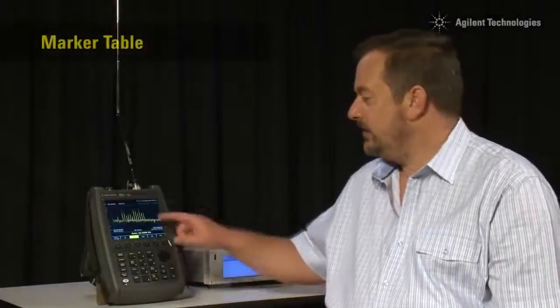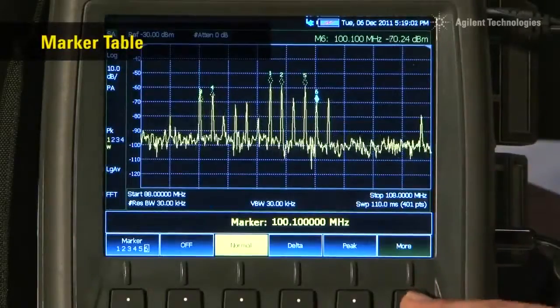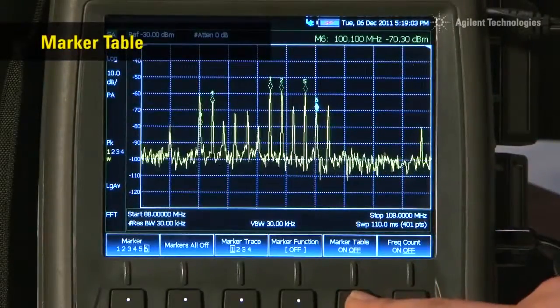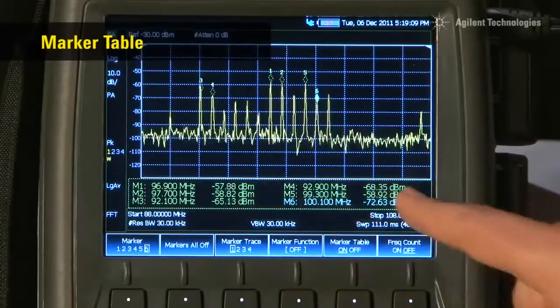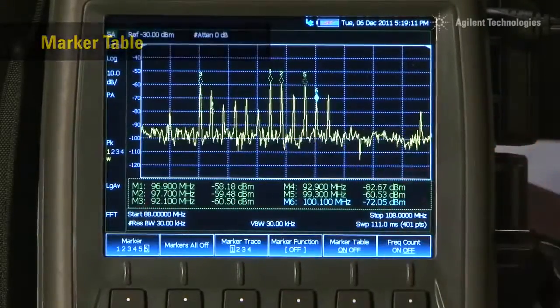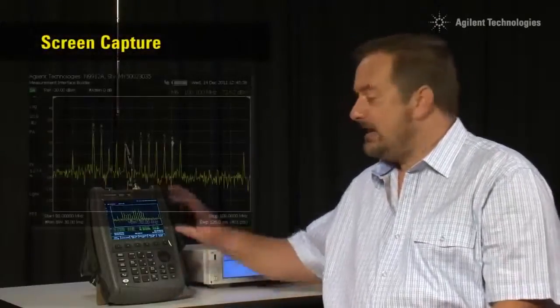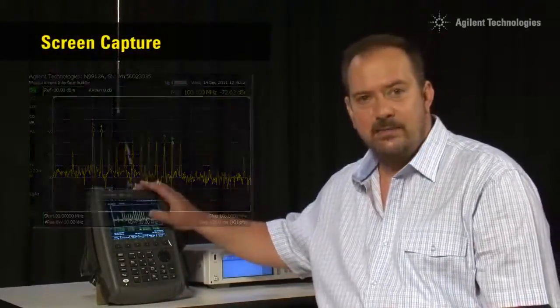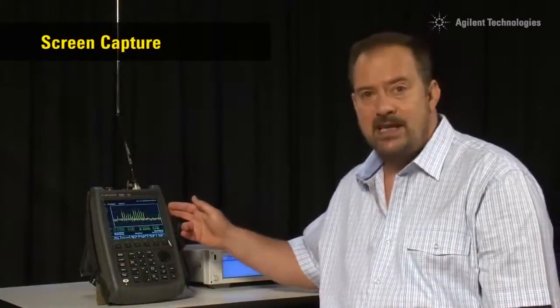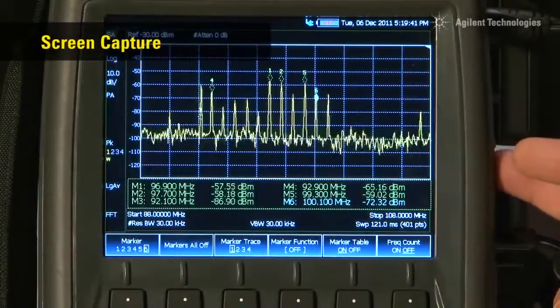And here you can see I have turned on all six markers, and if I press the More button, we can now turn on the marker table, which shows the frequency and amplitude levels of all six markers simultaneously. We can now capture that screen and save it as a JPEG file, either to the internal memory, to a USB memory stick, or the Mini SD card.